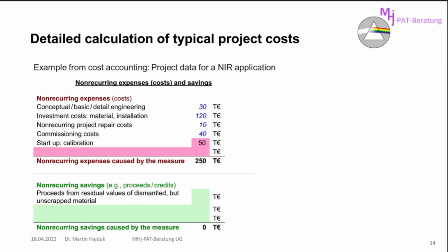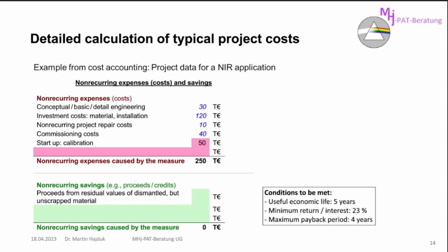Here's an example for a project with the NIR application. We started with the basic engineering, then we have around about 30,000 euros. Then we have the investment costs for the spectrometer, sample cells, glass fibers, and possibly the cabinet. Then something happened during our project, so we needed repair costs, and also commissioning costs for installation, connections, wiring, and transferring the signal to the DCS system. Last not least, we make the startup, and then we have to pay for the calibration, around about 50,000 euros.